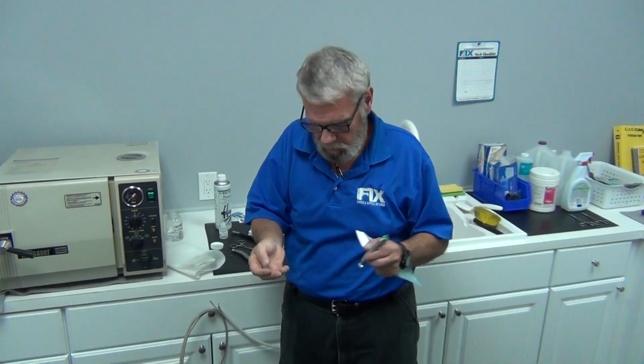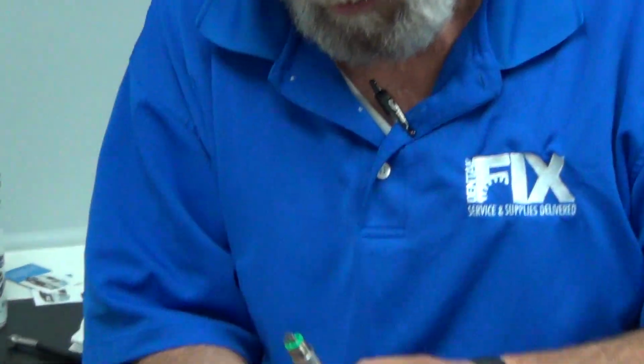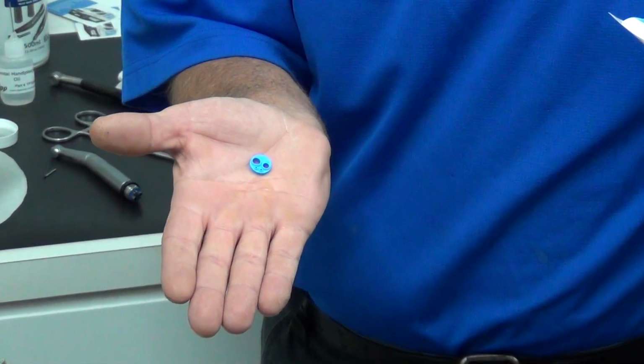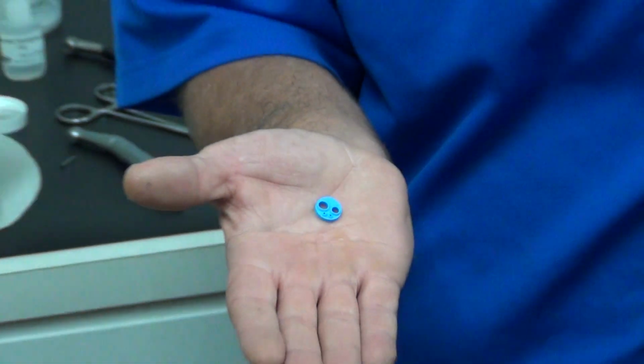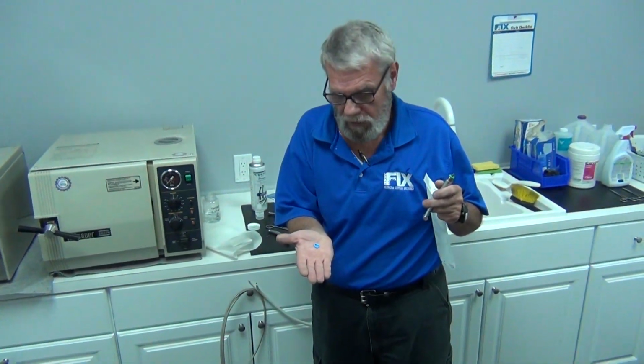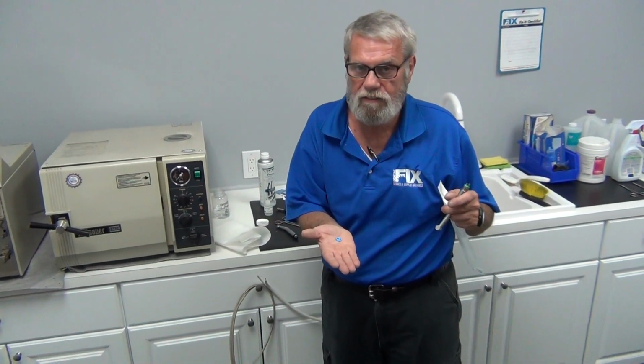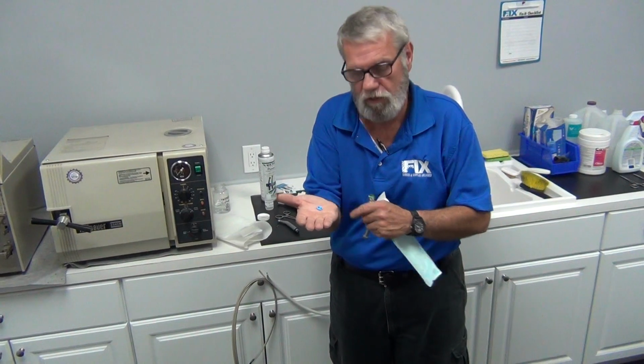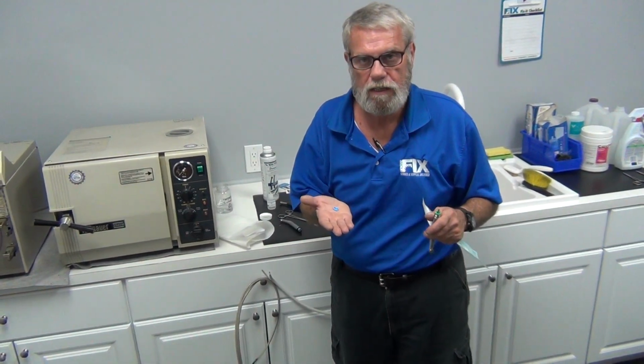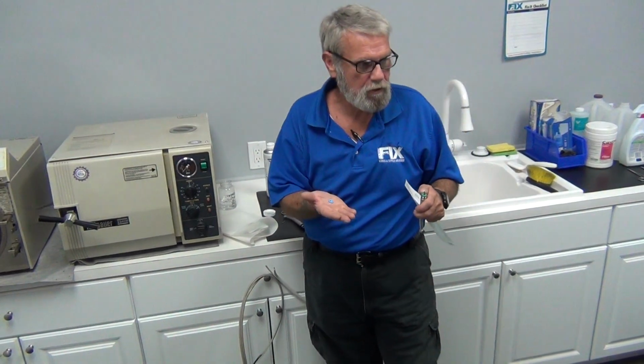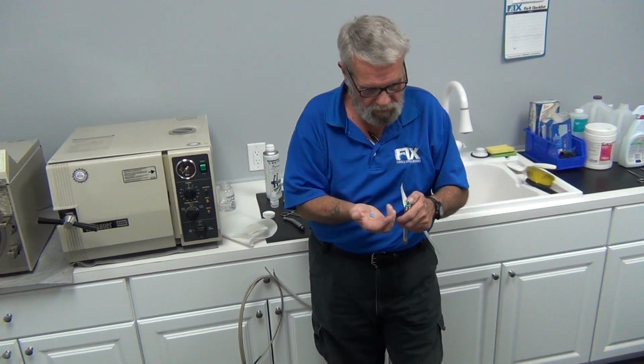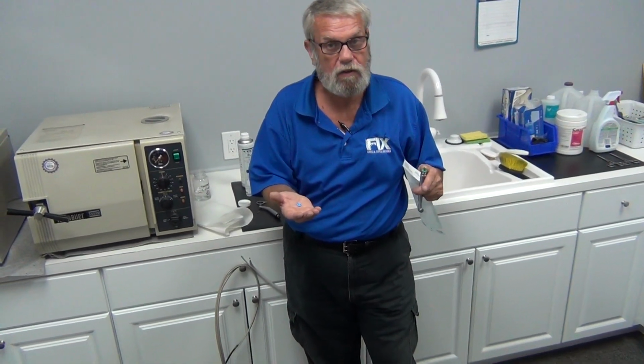I hope everyone can see. Let me hold it in my meat hooks here. Now, a lot of your problems are going to be due to no handpiece gasket or a bad handpiece gasket. You'll feel air between the connector and the handpiece on the delivery system. You'll also have spotty water spray, and you'll have water dripping down the doctor's wrist, all because the gasket's falling off. These gaskets tend to distort after so many sterilization cycles. They lose their retention and just fall off the back of the handpiece. It's very easy to throw them away. This handpiece will not work without a gasket. No handpiece will work without a gasket.